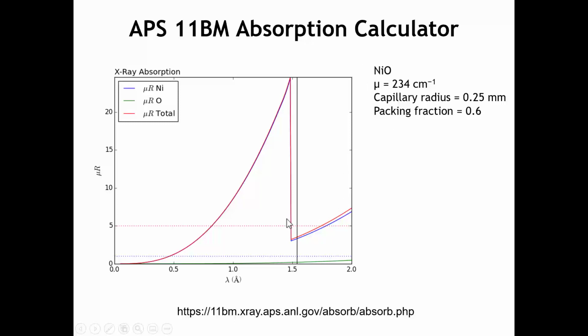The other thing that's not quite captured on here is that once you go past the absorption edge, let's say we were collecting right here, not only does the sample become pretty highly absorbing, but it also starts to fluoresce a lot. And that fluorescence will give you a larger background. So you really don't want to be collecting data at wavelengths that are just shorter than the absorption edge. And that happens with copper K alpha radiation when you collect data on cobalt and iron. And so those samples can be difficult to analyze with the diffractometer based on copper radiation. There are other elements, like some of the rare earth ions, that also are somewhat problematic with copper radiation.